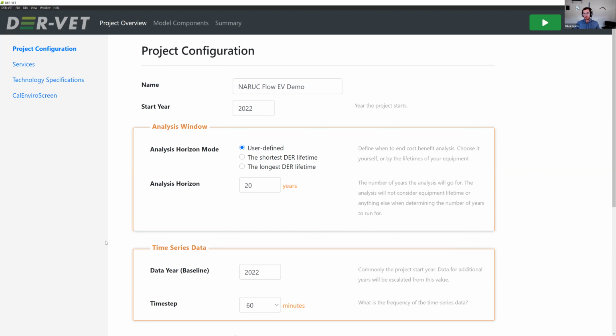Another feature we might see in some other storage systems or flow batteries is limits on the state of charge, but these are particularly relevant for lithium-ion battery systems, for example. We've set an upper limit of 100% state of charge and a lower limit of 0%, meaning all 400 megawatt hours we're modeling are usable. So we're not considering any kind of derating there.